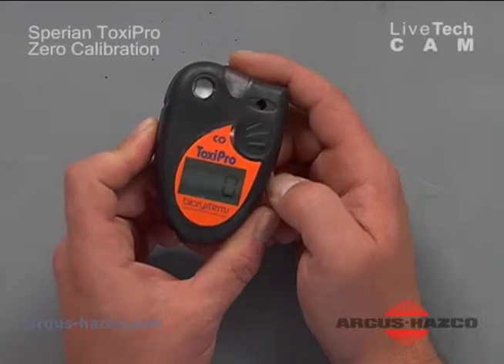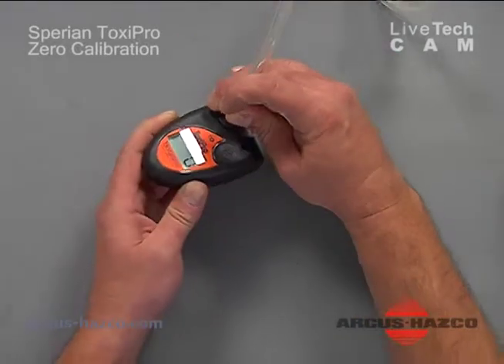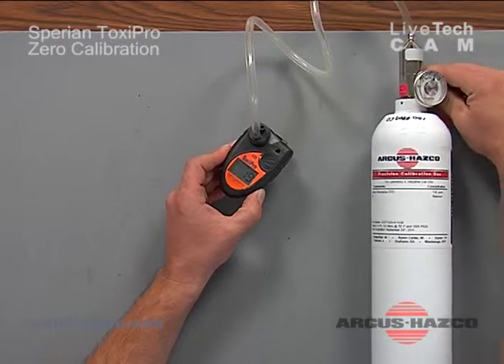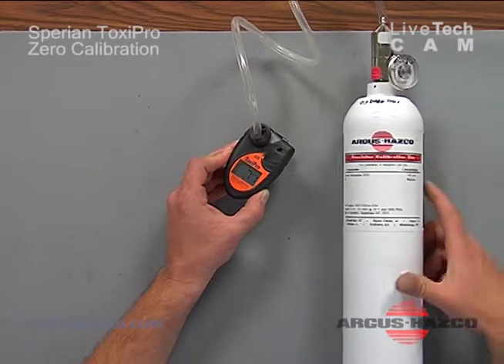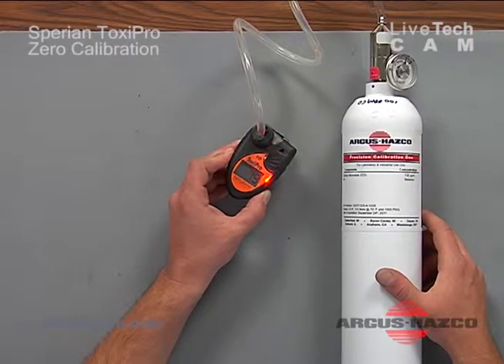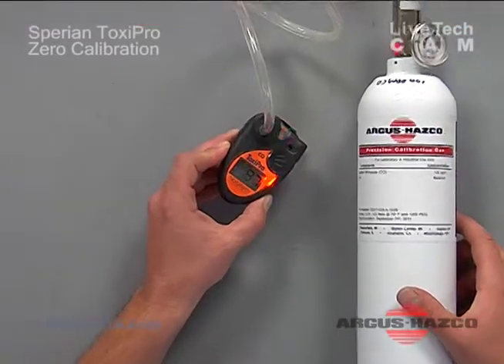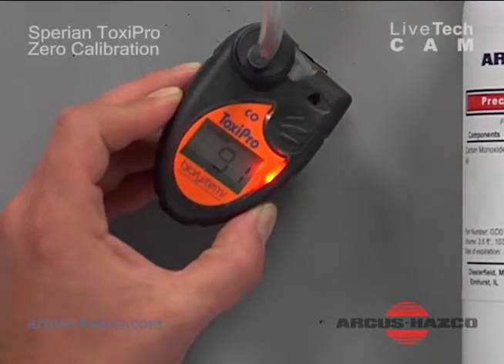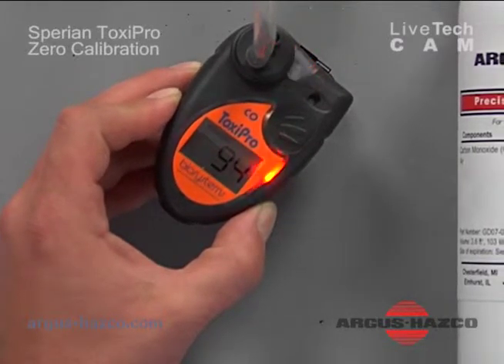What we'll do right now is a bump test. We'll apply our calibration gas to the unit — we're using 100 ppm CO. The unit value should match the gas within plus or minus 2%, and a low alarm will kick in. Audio, visible, and vibrating alarms will come on.